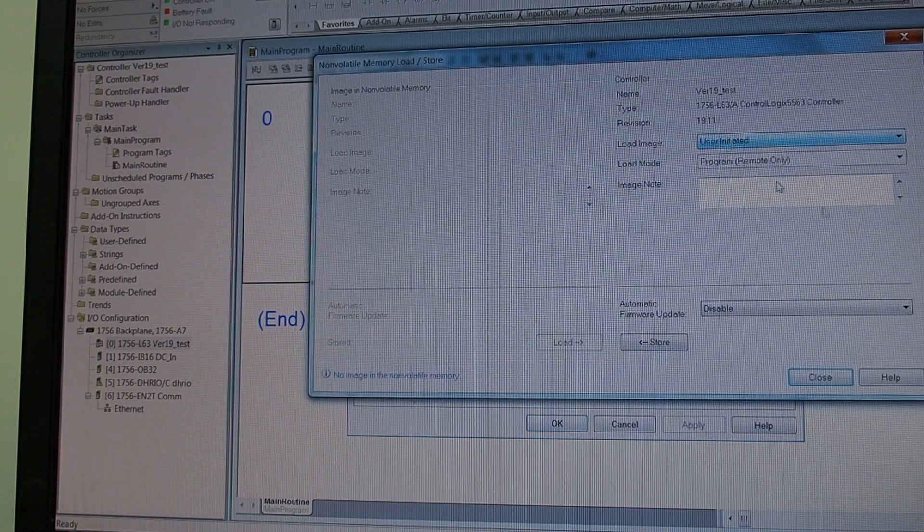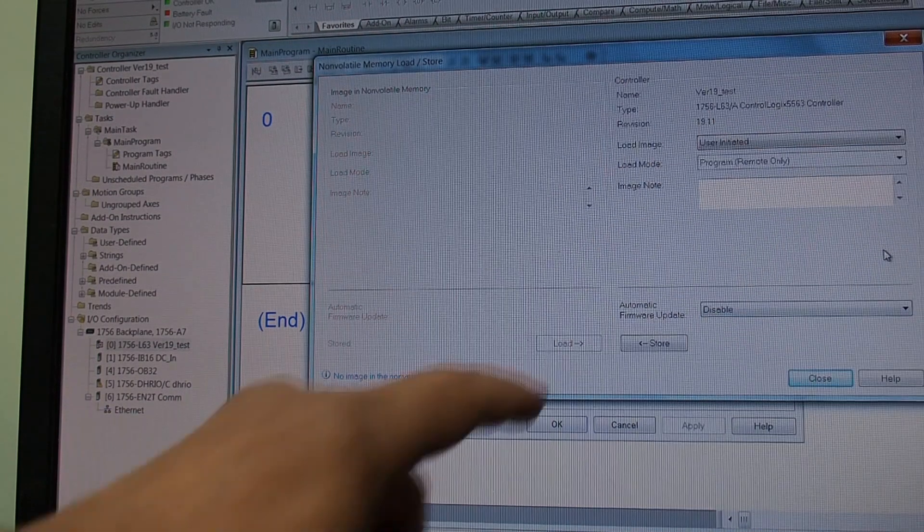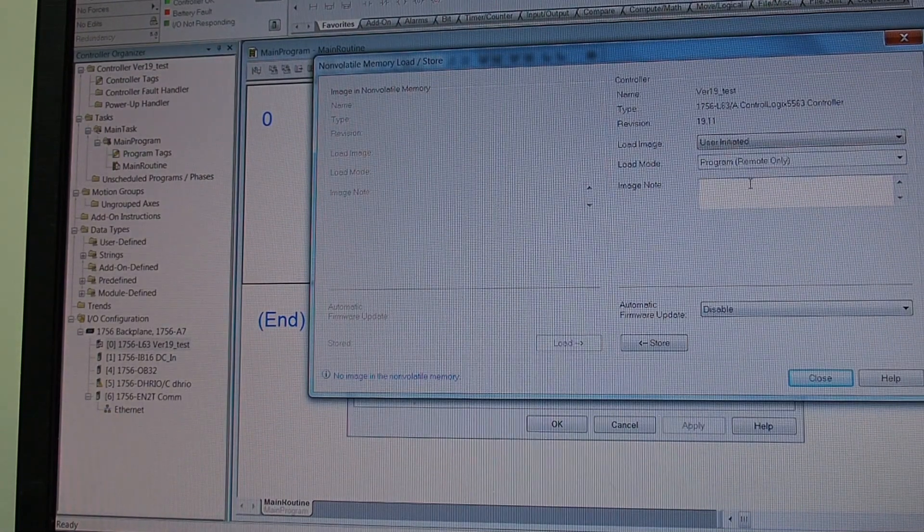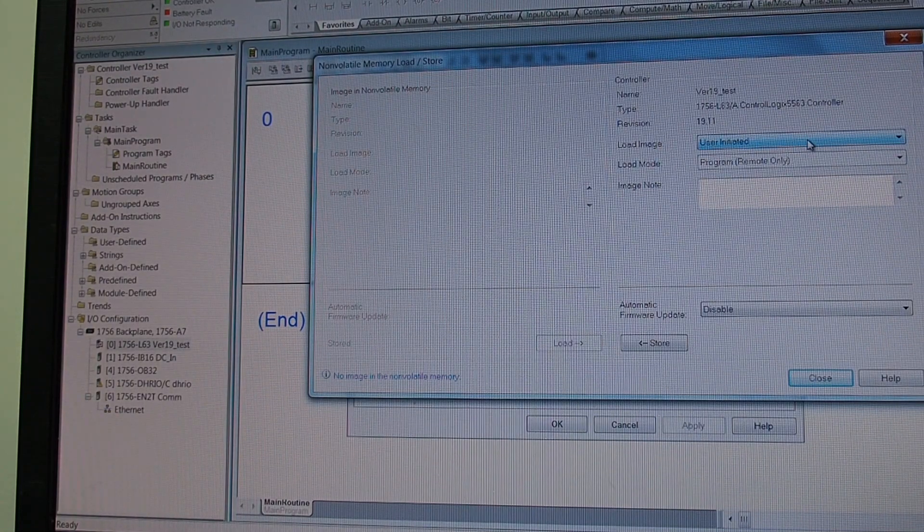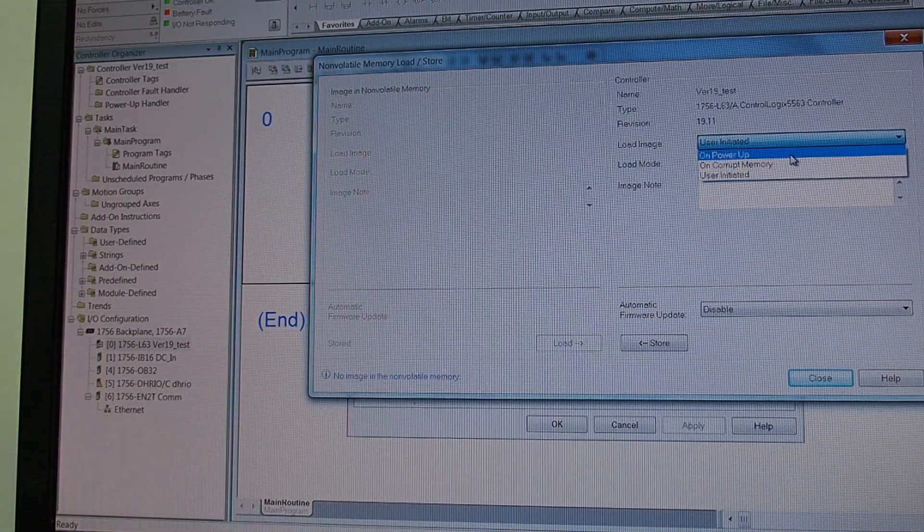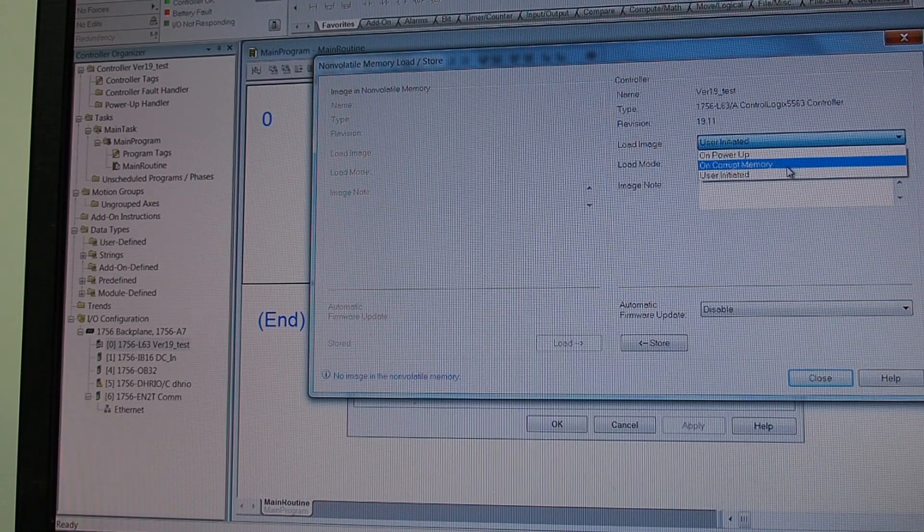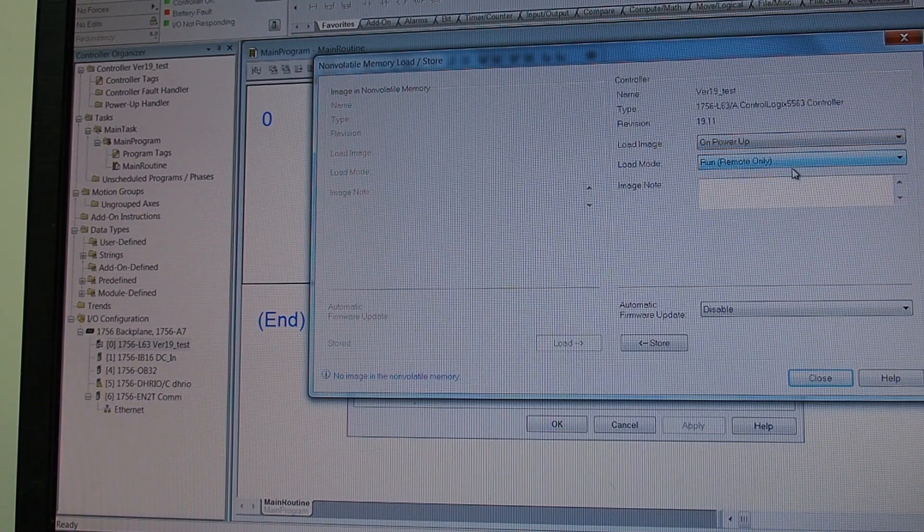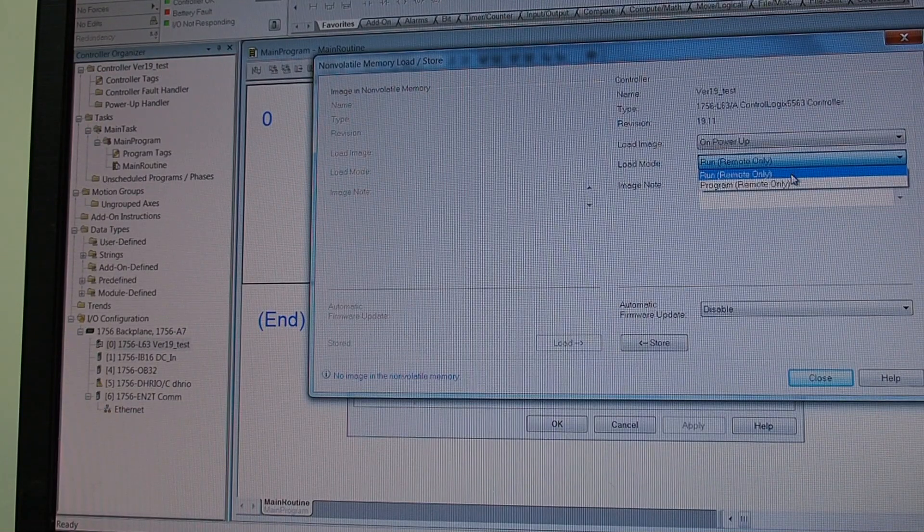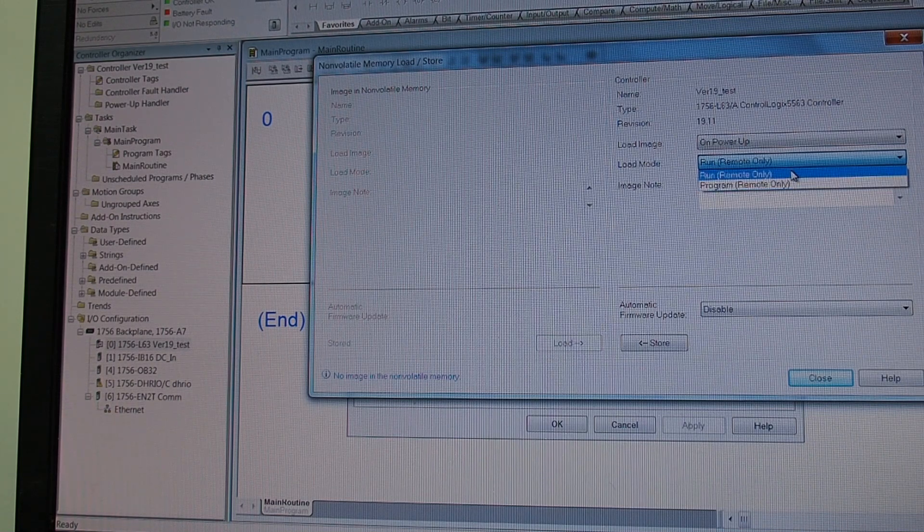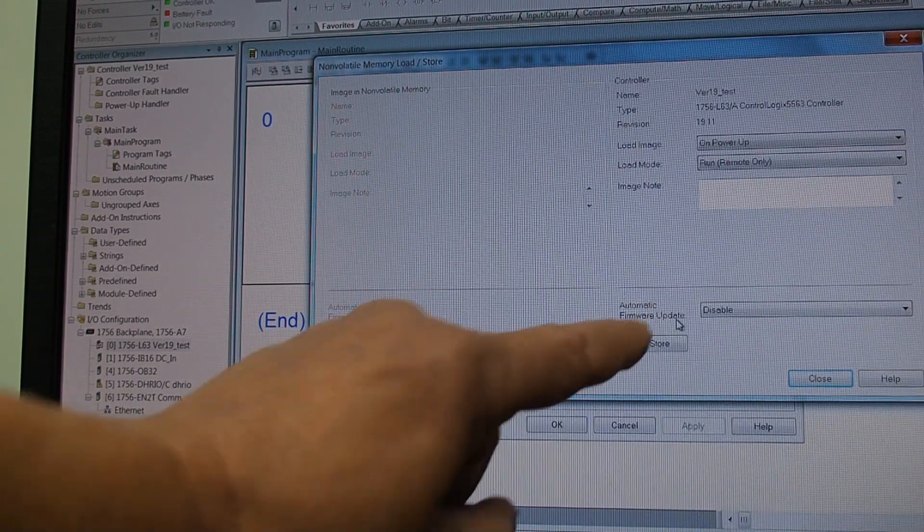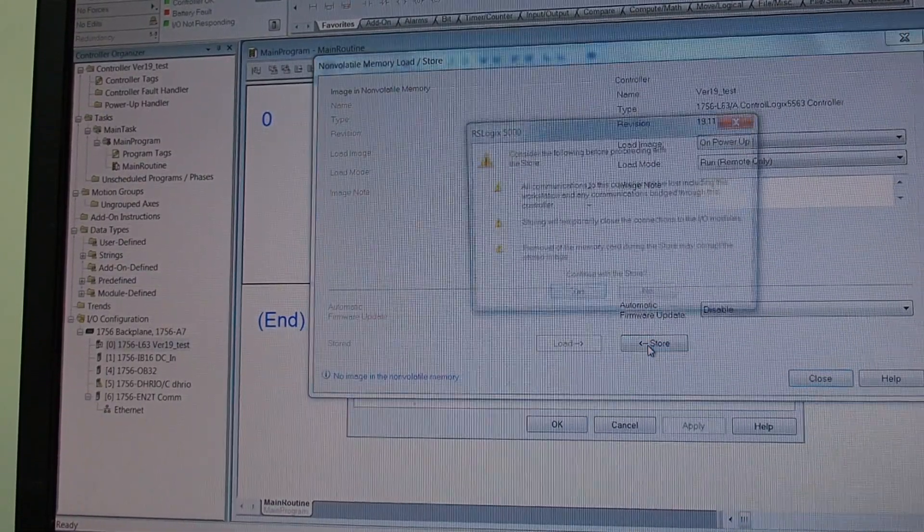So we go load store, power. Here is our controller on this side, here is our memory card on this side. A couple of things you want to set. First off, load image on power up is what we want to do here. Or it gives you the option of on corrupt memory or user initiated, we're going to do on power up. And the load mode will be run. We don't want to be in program, we want to just get back up and running and pumping the water or whatever we're doing. And again down here firmware is disabled and we tell it to store.